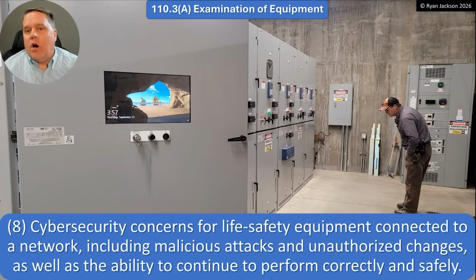So if we have a hospital where you can change the trip points of the circuit breakers using software, that's a little scary, especially if your machine doesn't even need to be connected to the switchgear. A lot of modern switchgear lets you connect your laptop right to it and change things like the trip points. That's fine, that's just as safe as walking up and doing it with a screwdriver.